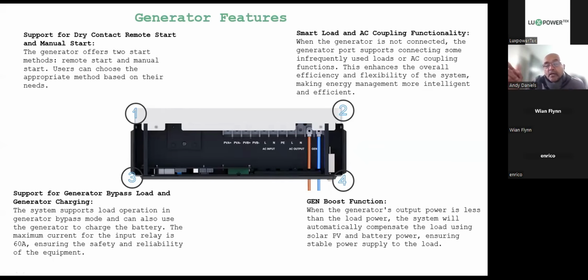Remember that we can only stop and start the generator. These are relays, right? So we have a normally open relay and we have a normally closed one. They share a common port. On the dry contact, it will be normally closed, common, and normally open. So one will be normally closed and one will be open. And when it gets to the flag, they will switch roles. And that's typically how it starts the generator. It's literally just a switch. Okay, there's no power coming from the generator to anywhere. You can run voltage through there, or if you're using it to power a relay or something like that, you can run voltage through there. It's the limit. Because it's a single line or single pole, you can either run AC or DC through there, but there are limitations as to how much switching current it can take. I think the maximum switching current it can take is 5 amps.